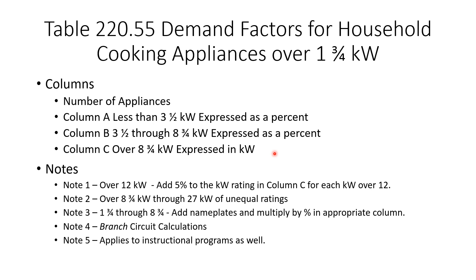In the table itself it says 'not over 12 kilowatts,' but Column C actually is used for over 12 kilowatts — you just have to do a little bit of math. You are going to use that column for over 12 kilowatts. That wording could be confusing and is something that might change in future editions.